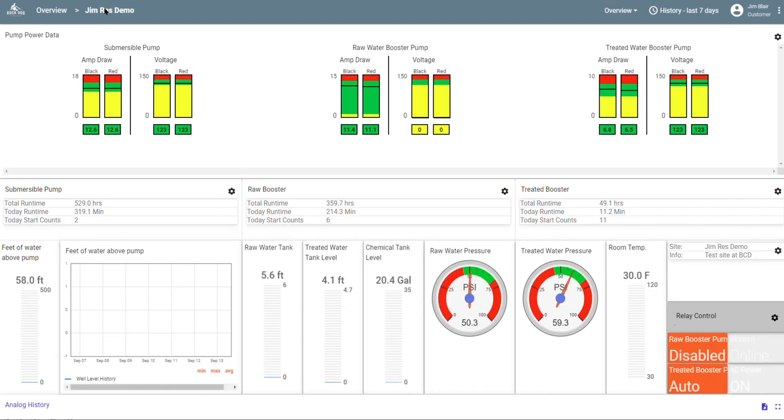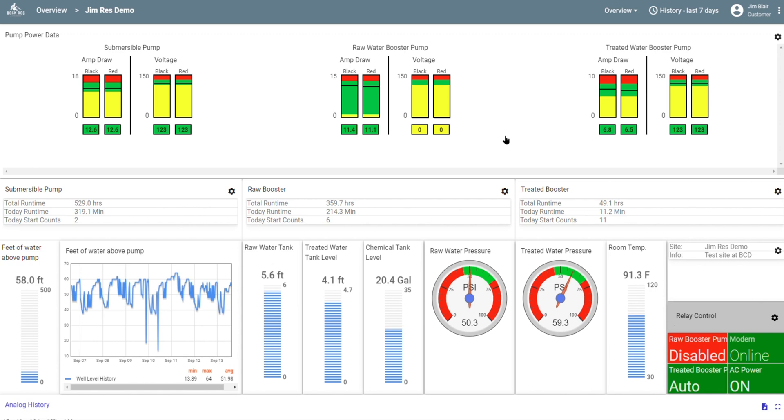If I go back to the main page, you can see that the voltage on that pump is now zero. About 10 seconds later, I get an alert by text and email that my power is too low on that pump. This is a pump man's best friend. Many of the high-tech controllers we have these days need to be reset to clear a fault condition. The way that we do that is turn the power off for a few minutes and that clears any faults. Now we can do that from our office and save you the expense of a service call.